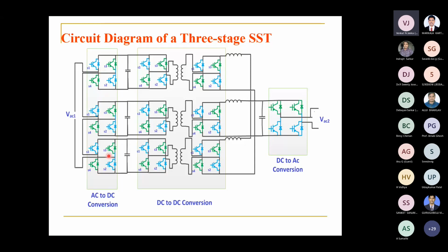On the primary side, it is a cascaded H-bridge converter, which can be utilized for the high voltage side, and it has multiple DC links. These DC links are stepped down using a dual active bridge, and all the dual active bridge secondaries are connected to a single DC, which is then converted back to low voltage AC using a DC to AC converter.